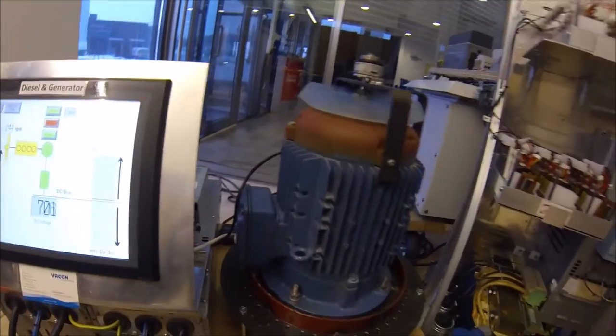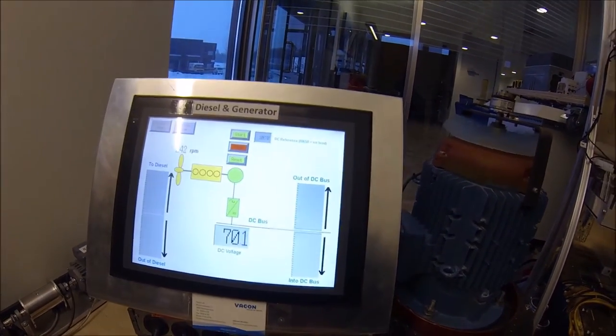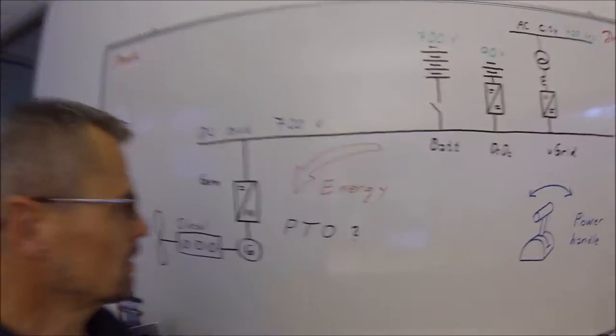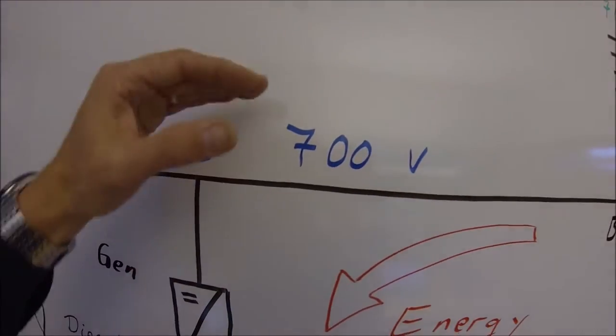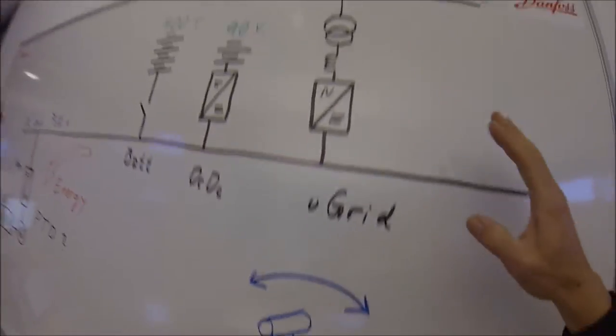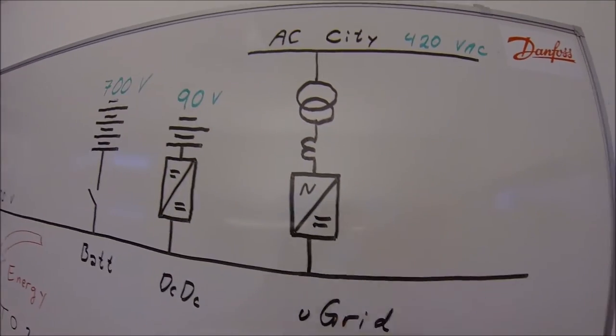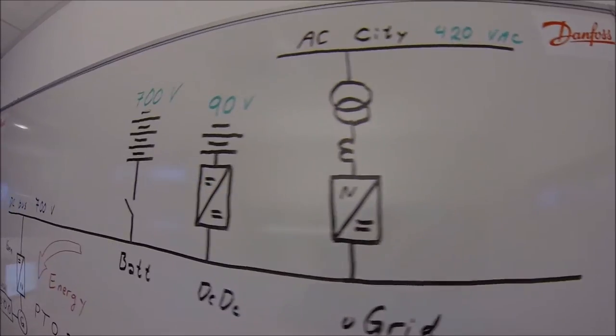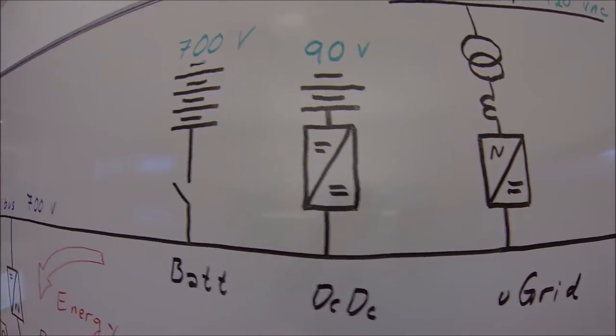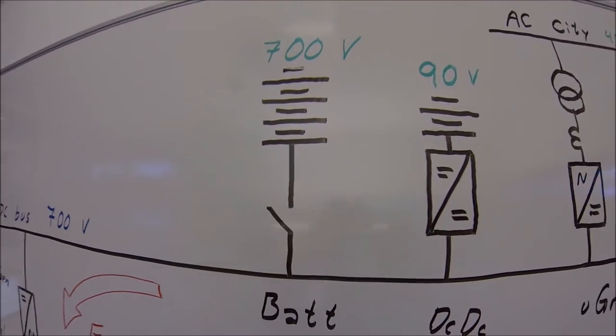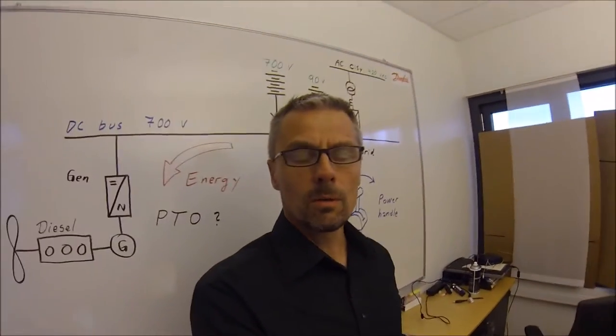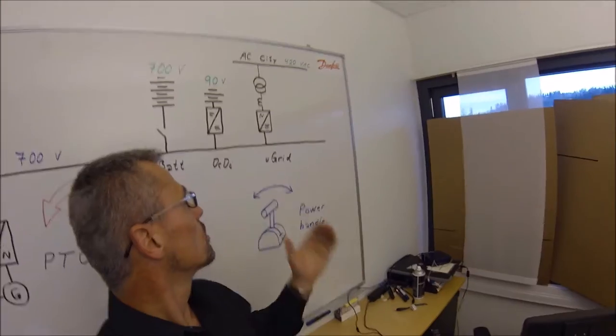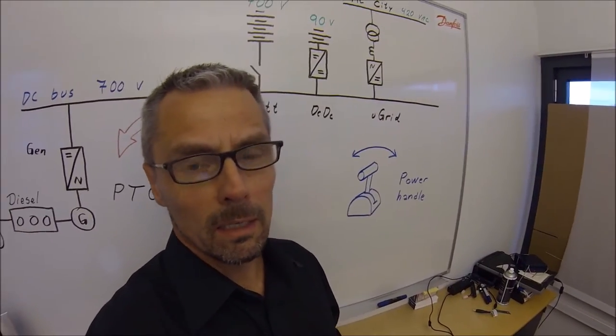The generator application will then sit in PTO mode and only be directed by the DC voltage. We have seen that even in power take-off mode you could add power to the ship propeller simply by increasing the voltage on the DC bus. With the U-grid application you can use the base current reference mode; with the DC-DC converter you can use the current reference handling mode. If you have an unregulated amount of energy with no power handle on the battery, it will just spin up in speed — quite brutal. In PTO mode you need to make sure you have the power handle on the energy source side of the system.